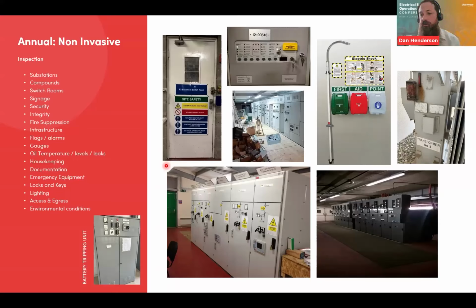One of the things I mentioned before and why it's important, there's a picture there on the right. It's an oil-filled transformer. Obviously, you can see that's leaking, so that would be something where I'd be identifying that, tracking it if it's not too bad, and then planning that in for my 5-yearly shutdown. As long as it doesn't get too bad, I would make sure I've got the parts, and I'll plan that in as part of my intrusive maintenance.